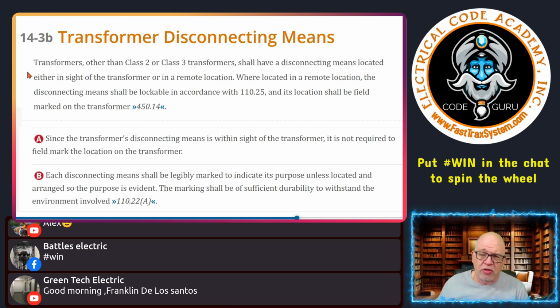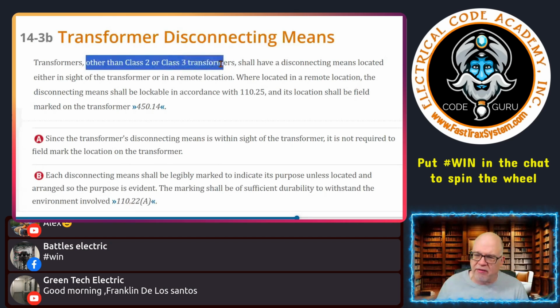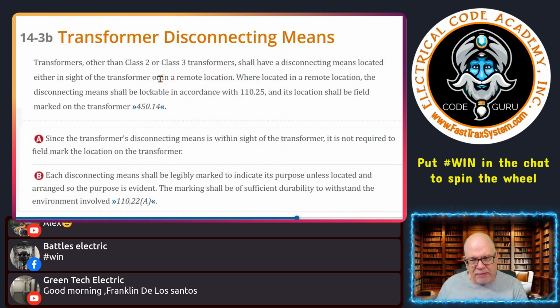So first of all, we're talking transformers. And when's the last time you saw a secondary or any disconnect for a class 2, for example a doorbell? You usually have the breaker for the branch circuit supplying the doorbell transformer. You have a primary side connection, which is 120, and then the output could be 24 volts, could be 12 volts, based on the transformer. That's typically what you see. So we're talking about transformers other than those that have limited voltage and current output, the regular transformers like you and I deal with every day. Well, I don't deal with them every day. You deal with them every day.